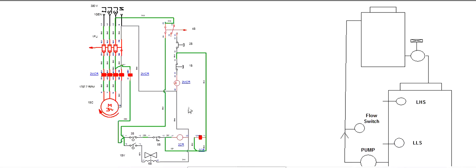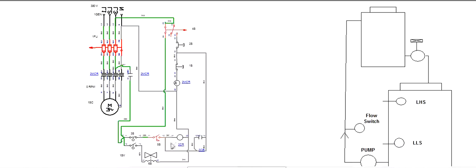When in auto mode you cannot even stop the motor — if you try to stop the motor it will come on again. Now why do I have this flow switch? For example, if there is no water in the tank and you run the pump, it will activate the switch and there is no water, it will stop the pump to protect the motor. If there is a flow it will activate — it should be normally open — when there is a flow it must run the motor.